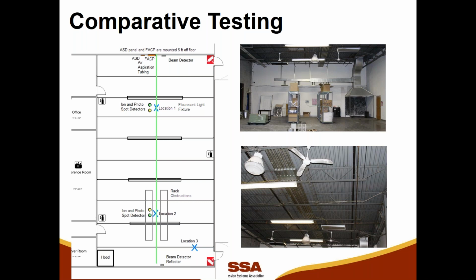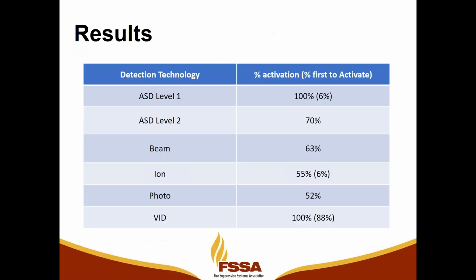Now, had this been an actual application where early detection between the racks was required, the camera could have been placed in the location that we're viewing now to see the smoke rising from the floor. So video analytics detected 100% of the fires, and 88% of the time first. And you can see why. The analytics is analyzing the image floor to ceiling. As the smoke rises, as soon as it hits the alarm zone, it goes into alarm.